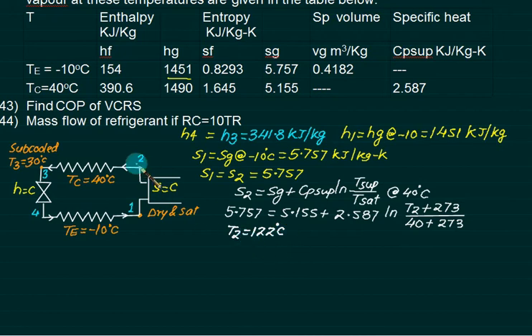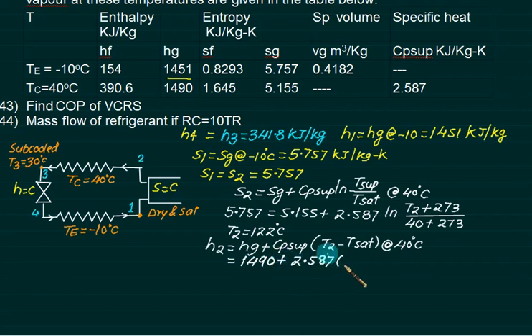Can we calculate enthalpy at point number 2? Point 2 is superheated. We have H2 equals Hg plus Cp soup into T2 minus T saturation. For 2, you have to take value at 40. Hg at 40 is 1490 plus Cp soup. T2 we just confirmed is 122, so this is 1702 kilojoules.